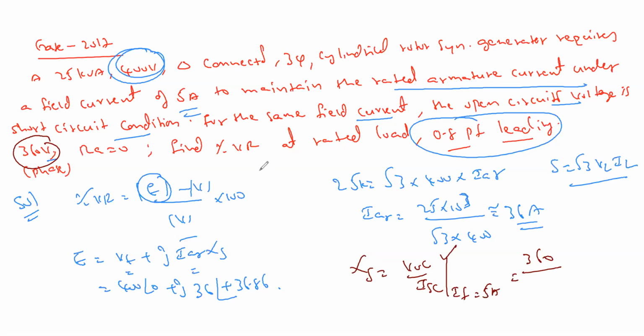Short circuit rated current - what we are getting here is line current only. So I want the phase current, not this 36 value. Now, what is the phase current here? 36 by root 3, since root 3 VL IL, so phase current comes out to 20.78.